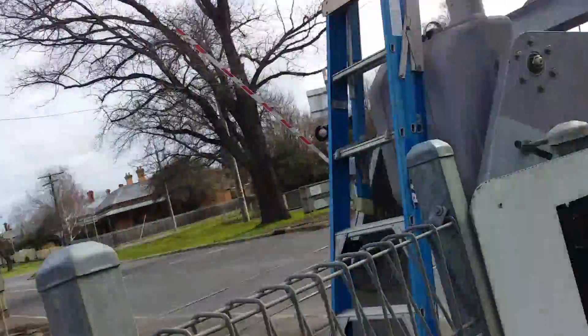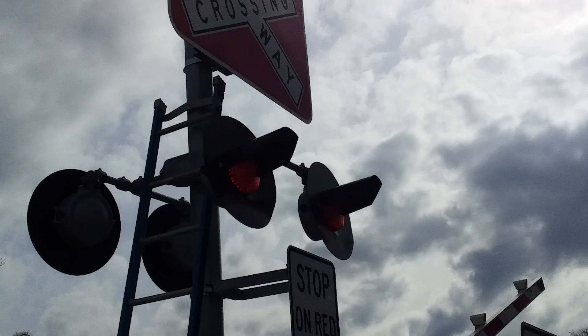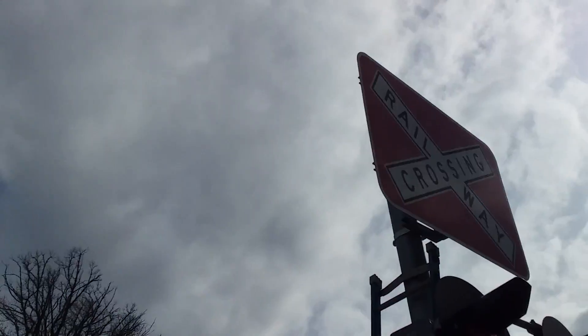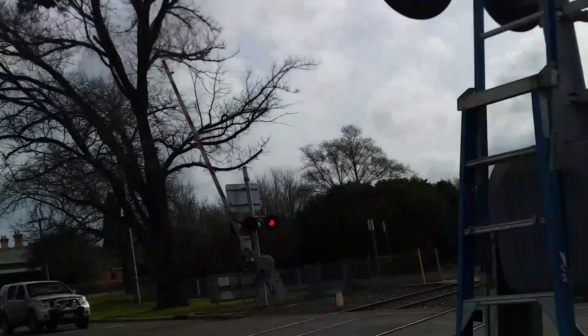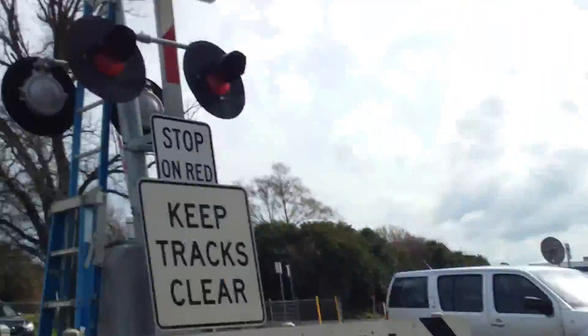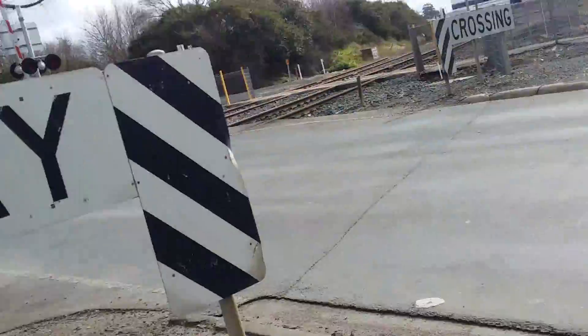I've come up to the signal to see if it's working — it's not working. I can hear the bell on the other side but this one is still silent. So they're going to have to do a bit of work on it. Lucky day I'm having today. They pushed the test switch button back in and the boom gates have gone up again — they've got a bit more wiring work to do.